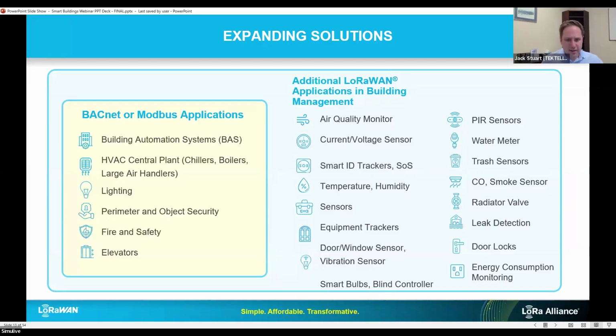Once LoRaWAN is integrated into a BACnet-based smart building, the number of use cases available to the building operator expands dramatically. BACnet systems today typically manage HVAC, lighting, and security—critical systems that will continue to be critical. But with LoRaWAN, you can now add occupancy sensors, asset trackers, air quality monitors, leak detectors, smart thermostats, and much more, all without changing the core system operating the building.